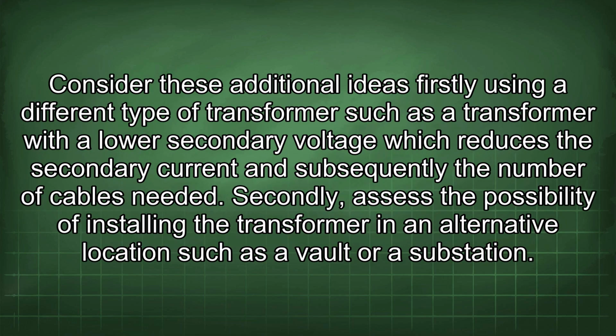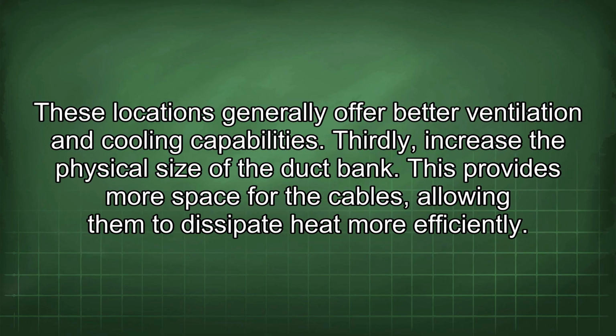Consider these additional ideas. Firstly, using a different type of transformer, such as a transformer with a lower secondary voltage, which reduces the secondary current and subsequently the number of cables needed. Secondly, assess the possibility of installing the transformer in an alternative location, such as a vault or a substation. These locations generally offer better ventilation and cooling capabilities. Thirdly, increase the physical size of the duct bank. This provides more space for the cables, allowing them to dissipate heat more efficiently.